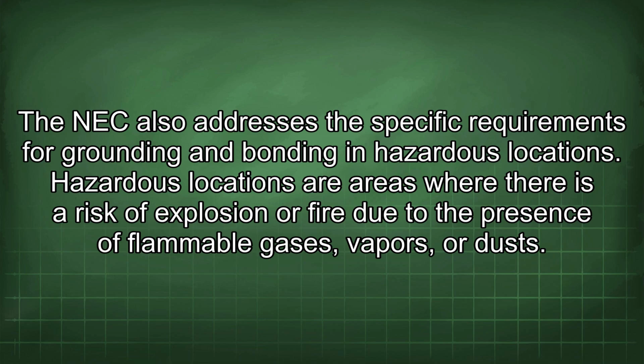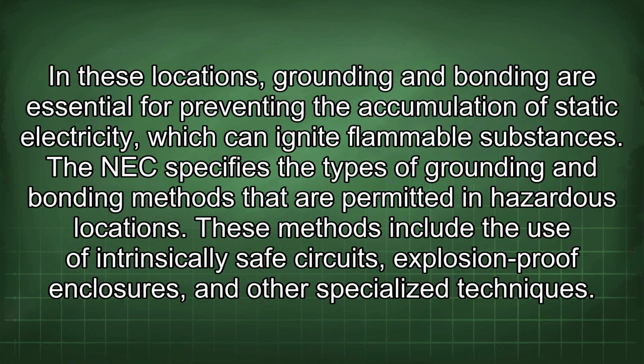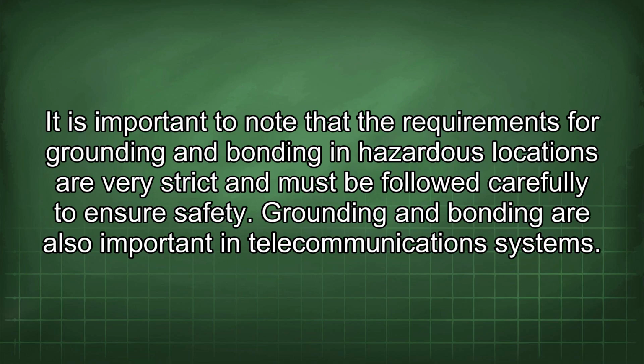Hazardous locations are areas where there is a risk of explosion or fire due to the presence of flammable gases, vapors, or dusts. In these locations, grounding and bonding are essential for preventing the accumulation of static electricity, which can ignite flammable substances. The NEC specifies the types of grounding and bonding methods that are permitted in hazardous locations. These methods include the use of intrinsically safe circuits, explosion-proof enclosures, and other specialized techniques. It is important to note that the requirements for grounding and bonding in hazardous locations are very strict and must be followed carefully to ensure safety.